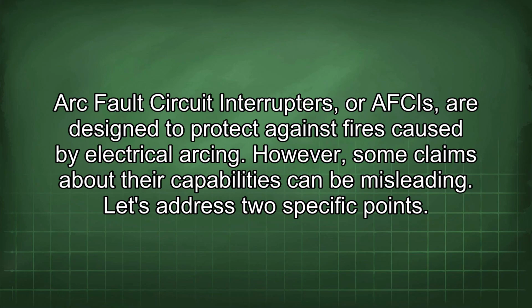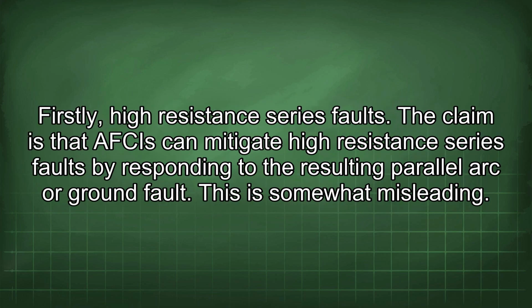Arc fault circuit interrupters, or AFCIs, are designed to protect against fires caused by electrical arcing. However, some claims about their capabilities can be misleading. Let's address two specific points. Firstly, high-resistance series faults. The claim is that AFCIs can mitigate high-resistance series faults by responding to the resulting parallel arc or ground fault. This is somewhat misleading.